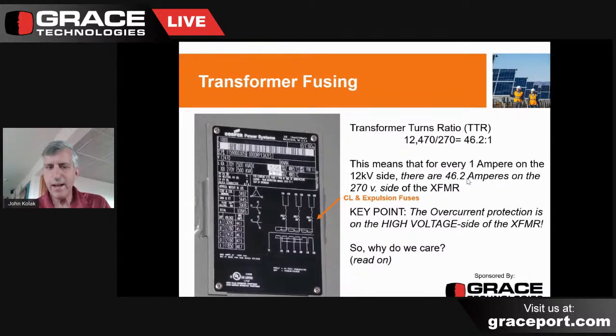So if you only had expulsion fuses and those well fuses that I showed you earlier, a fault on the primary winding, the high voltage winding, would be a through fault. It would not be able to interrupt the current flow, and the fault would go all the way back to the substation. You'd actually have to clear the entire 34.5 circuit in order to clear that.